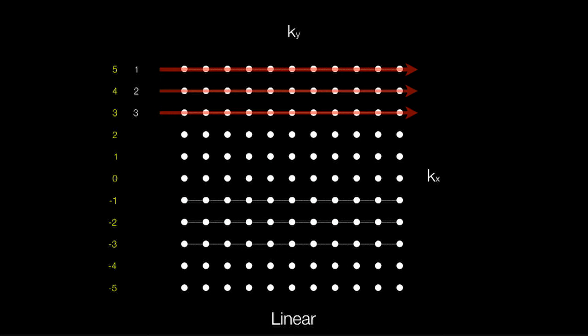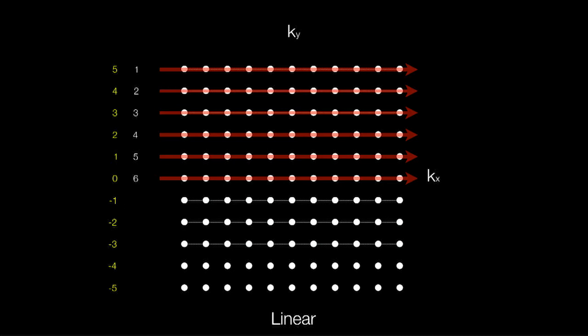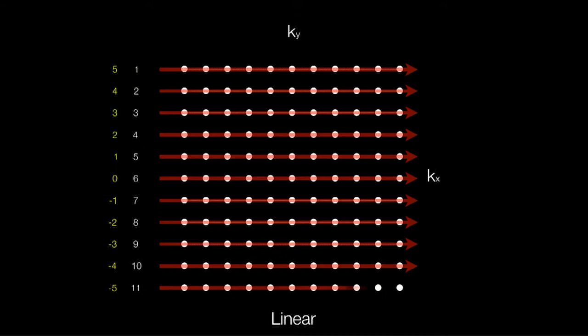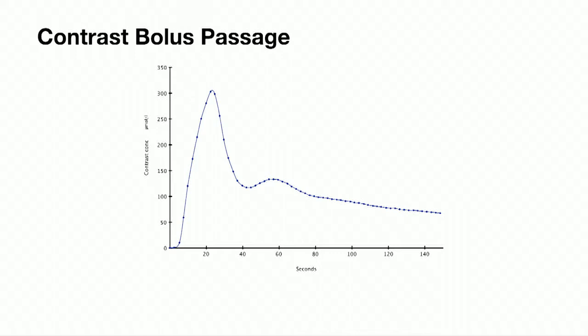In linear K-space, which is the conventional way we collect K-space, we collect each line starting with the peripheral lines and only hit the centre of K-space about halfway through the acquisition. Everything up to that point has been mainly peripheral, and if you're talking about multiple seconds of acquisition, that can have a real impact on how you collect your contrast and how you time it to your bolus.